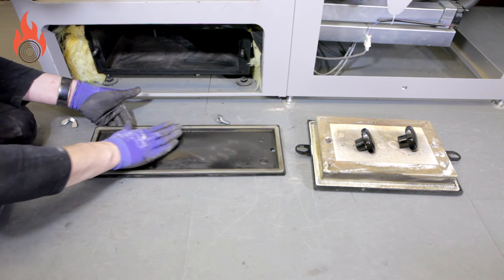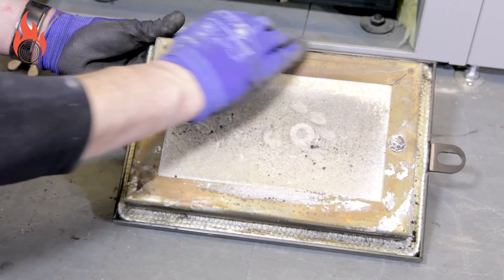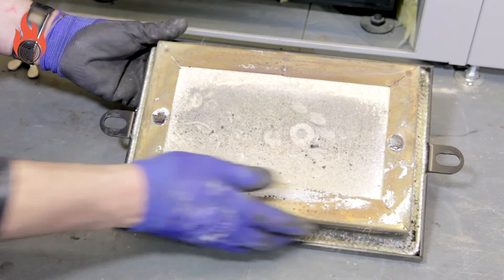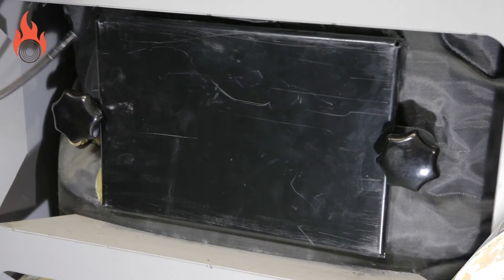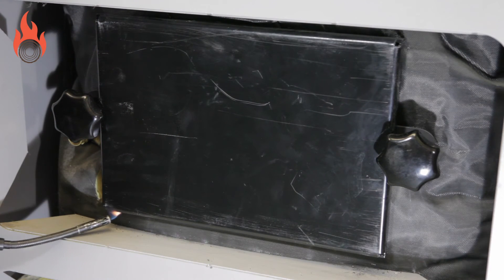Before closing up the boiler, you will need to check the door seals. The upper combustion chamber door uses rope seal and the lower ash chamber door uses a rubber seal. To check if there is a good seal around each door, close the doors and then turn on the induced draft fan.